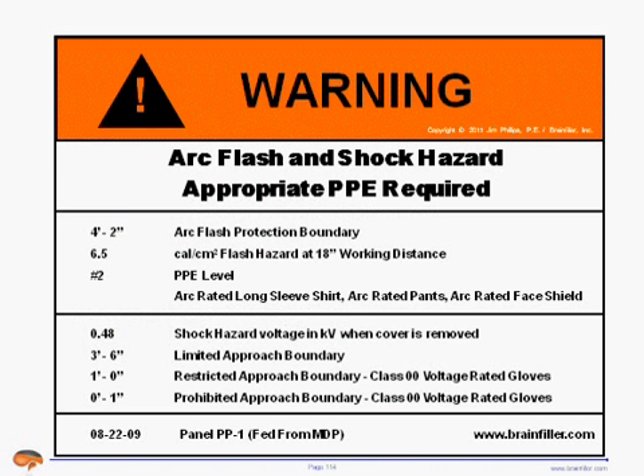And right now, there are a lot of different ways to produce a label. In fact, there's going to be a new annex in the back of NFPA 70E that's going to give some of the labeling options. And a lot of the software produces labels such as what I have on the screen. Not all of this is required, and some choose to use it all, some choose not to. Item number 1, that meets the requirement of the National Electrical Code where you have a warning label. Item number 2, this is the arc flash protection boundary, which is going to be relabeled arc flash boundary.